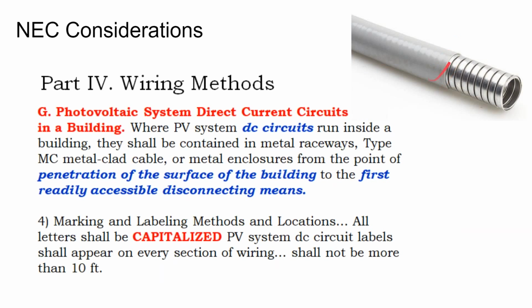Here is a plastic wrapped metal conduit. We have to remember that code requires DC circuits inside of buildings to be contained in a metal raceway. And then that metal raceway can't be exposed to the corrosive gas of the batteries. And so this is called a liquid tight flexible metal conduit. It's the most expensive kind of flex conduit. So you can buy metal flex that doesn't have this plastic wrapping. You can buy non-metallic flex, which is really just this wrapping. You combine the two together, that's where it starts to get expensive, but that's kind of the nicer product for running your battery cables through back to the inverter from your battery enclosure.